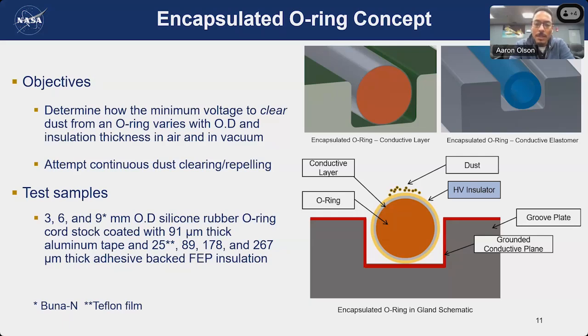This could also be done with a conductive elastomer. If you replace the O-ring shown in orange in the graphics on the right, you can connect a high voltage power supply to the conductive elastomer and remove the need for a conductive wrap before installation.